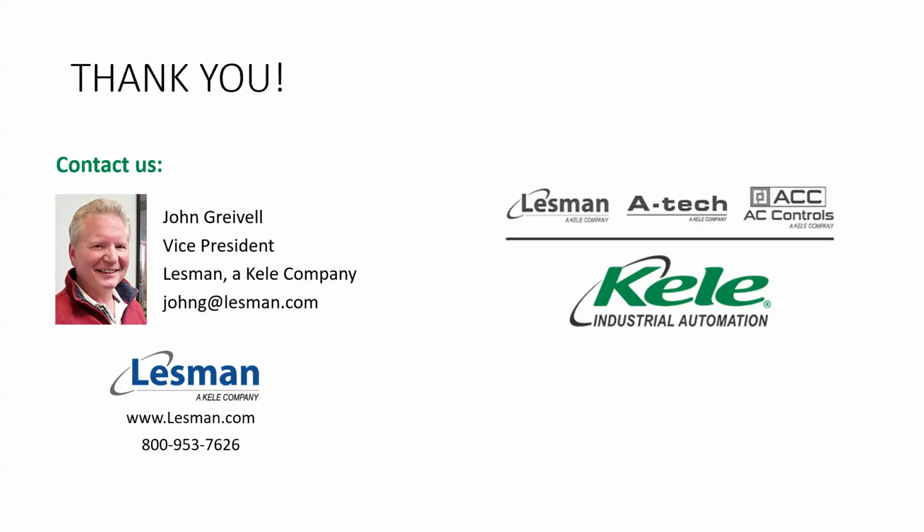The other portion of the question is confirming that you could use one transmitter and 3 sensing points. Can you just review that one more time? So if you have 3 sensors, you could have 3 LEL sensors. One of them has to be an Optima Plus. The other 2 could be catalytics or toxics or a mix. You can mix and match any way you like on the 3 sensors as long as one of them is an Optima. So you can literally have 2 oxygen sensors or a methane and oxygen sensor or whatever configuration you like. Again, it's a single sensor, a dual sensor, or a 3 sensor configuration. Once you get in that 3 sensor configuration, one of them has to be an Optima. The other 2 can be any gas of your choosing.